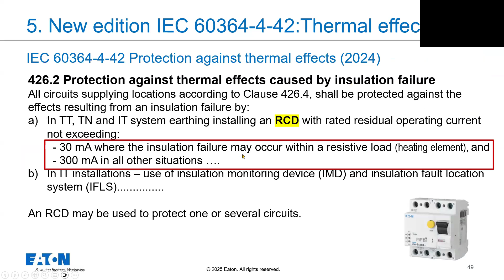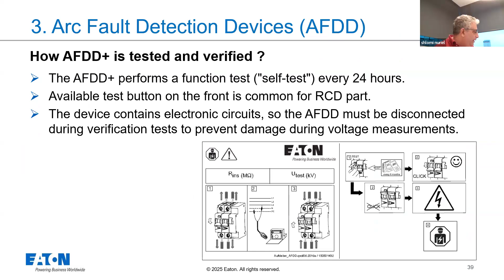Yes, I can explain shortly, maybe a picture is best, also regarding the short circuit capability of the device - is it 10 kiloamps or? Look at this picture, from the front printing we can read all the important features; we have more variants. You can see this device has an MCB part with 6 kiloamps breaking capacity, and rated current up to 40 amps.